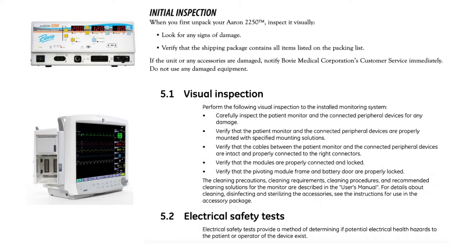Almost always the first thing done when receiving a new medical device, or as part of a preventative maintenance routine, includes using your eyes to inspect the device for issues such as checking the housing for damage, looking for fluid contamination, and looking for obviously broken parts. Of course, what's included in the inspection varies by medical device, and some manufacturers will provide specific guidelines.